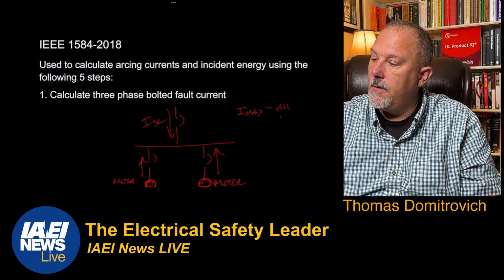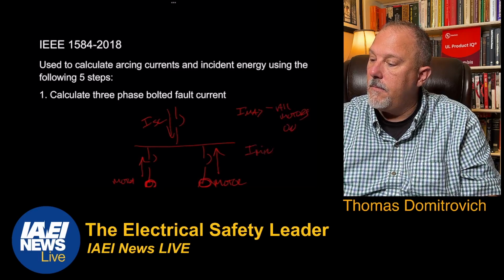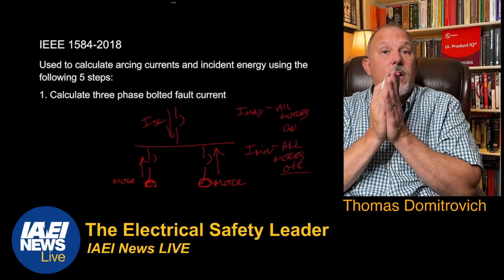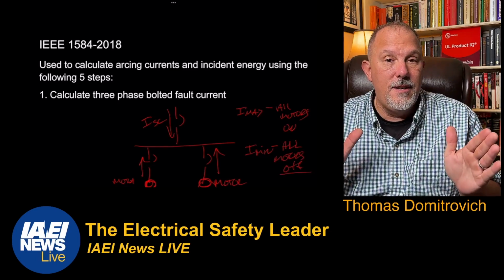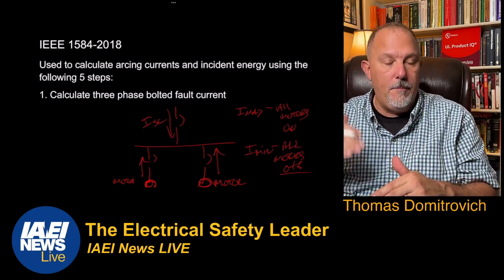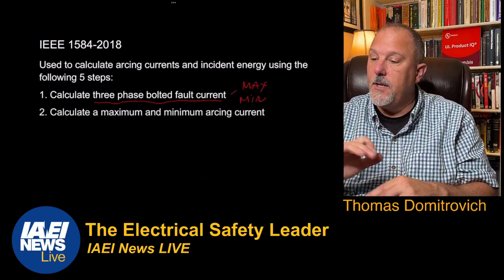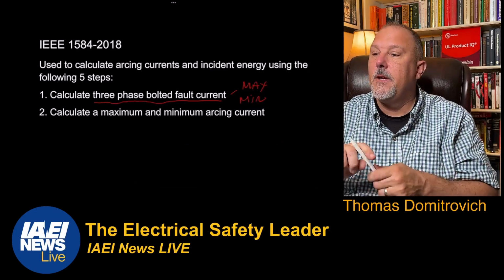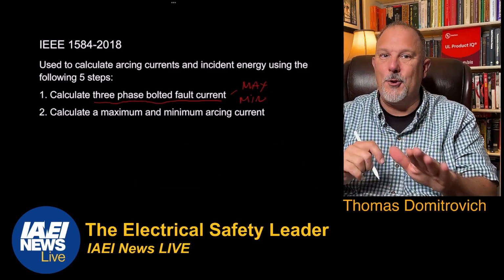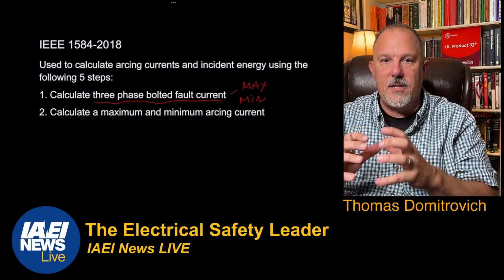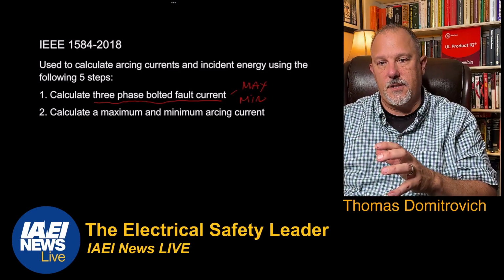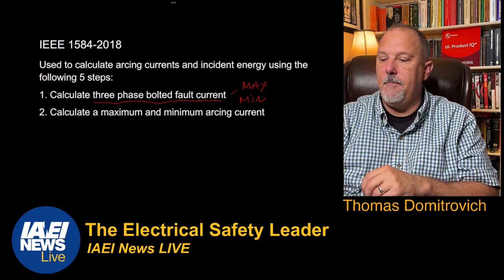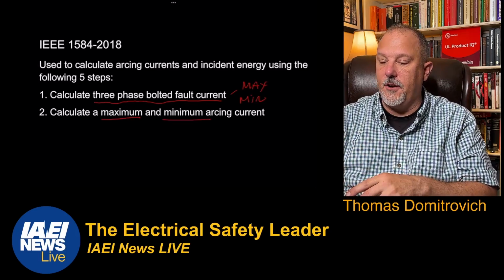So what I would want to do is, for I max, all motors on. For I minimum, all motors off. That's one of the simplest examples of a maximum and a minimum fault current value, the bolted fault current value. You'll understand why this is important as we move through this discussion. So we're going to calculate a maximum and a minimum arcing current value.